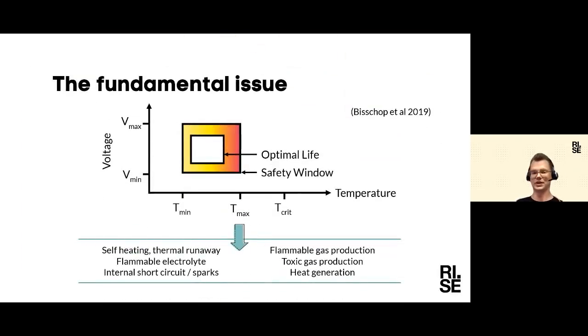The issue with these individual battery cells inside the battery pack is that they have a fundamental issue: if you exceed certain operational limits, you may at some point introduce damage or trigger degradation mechanisms inside the battery cell that could immediately cause issues, or in a longer period of time cause issues, or may also not cause issues at all. But when issues are caused, they can be very severe.